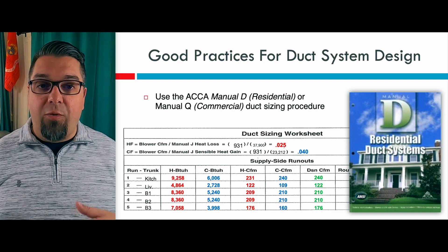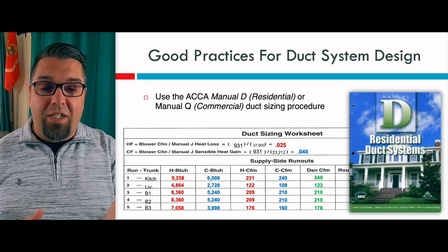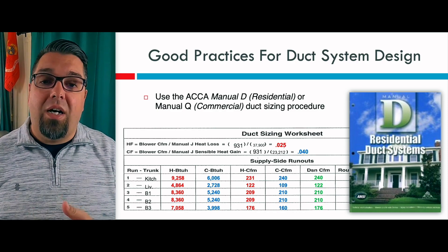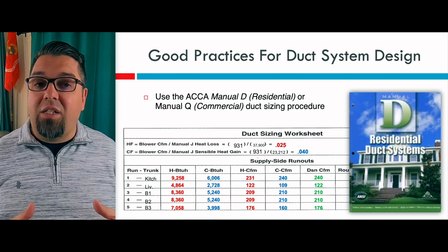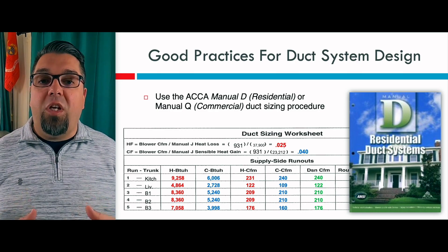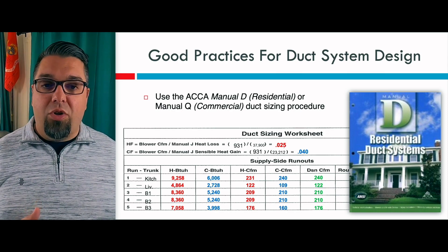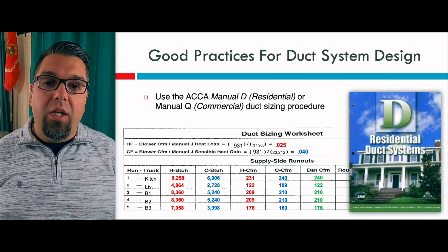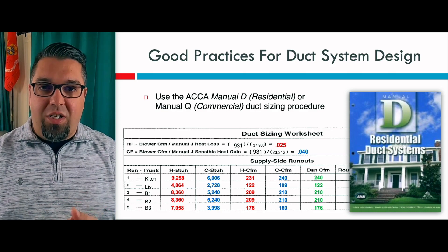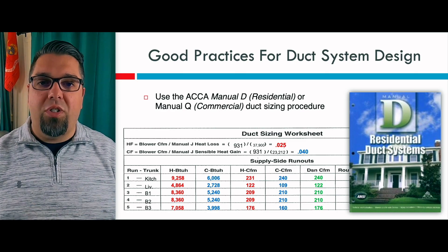You're going to use ACCA Manual D for residential duct sizing procedures. As you can see here, this is a screenshot out of one of my duct design classes — if you're an elite member on Patreon, you have access to this design class. This is a duct sizing worksheet where you walk through the heat loss and sensible heat gain for each room, figure the volume of air that needs to go to each room, and then use a duct calculator to size the runs. Those are the three basics: you've got to do the system design manuals first — it goes J, S, then D.